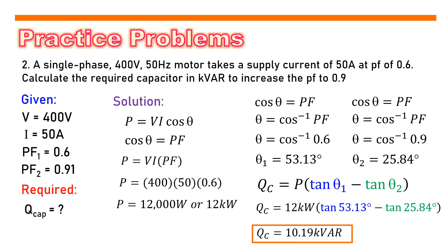Since meron na tayong power, cosine theta is equals to power factor. Kukunin uli natin yung theta 1, that is equals to 53.13 degrees. Para ma-increase natin sa 0.9, kailangan natin makuha yung theta na equivalent to 0.9, that is equals to 25.84 degrees. Using our equation again, substitute all the values na nakuha natin: 12 kilowatts multiplied by tangent 53.13 minus tangent 25.84 degrees, and that will give us 10.19 kVAR na required capacitor bank size.